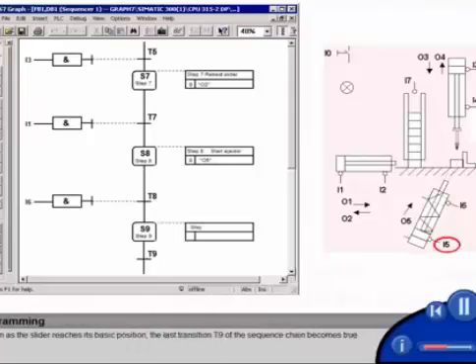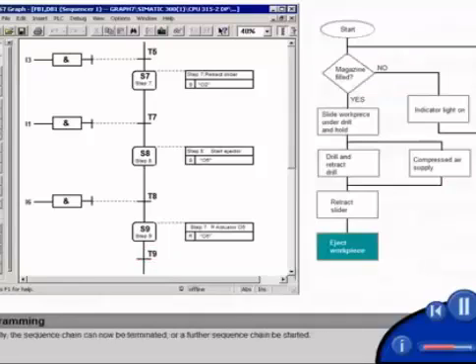As soon as the slider reaches its basic position, the last transition T9 of the sequence chain becomes true. Basically the sequence chain can now be terminated, or a further sequence chain be started. In our example, the chain is processed cyclically, meaning another work operation starts in the first step S1 of the sequence chain.